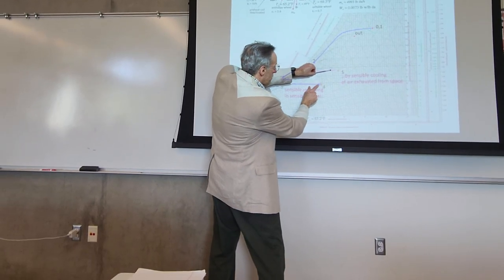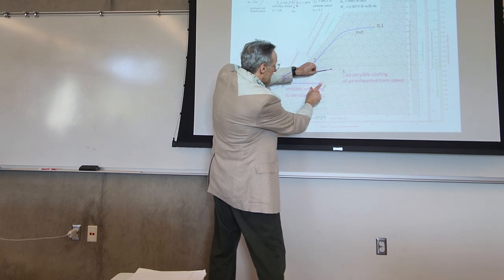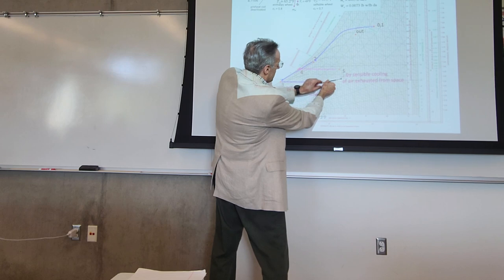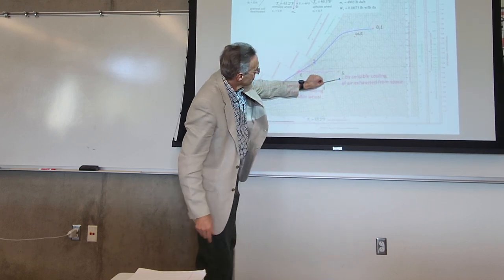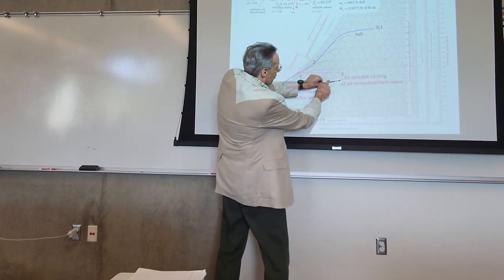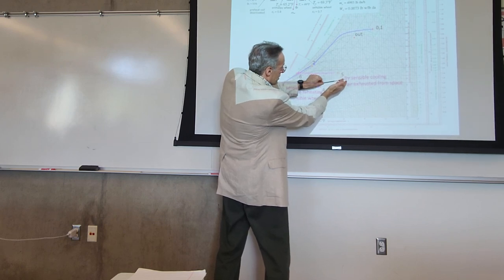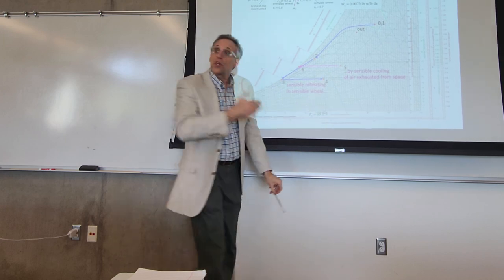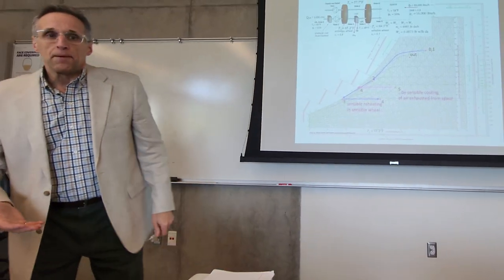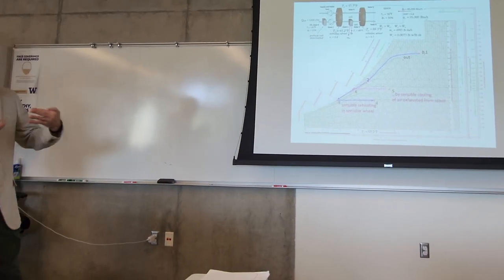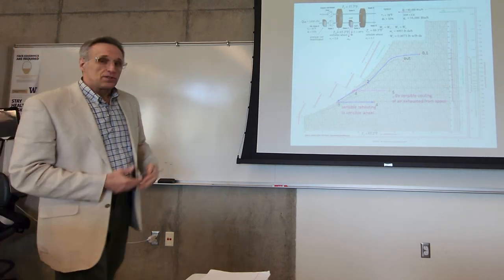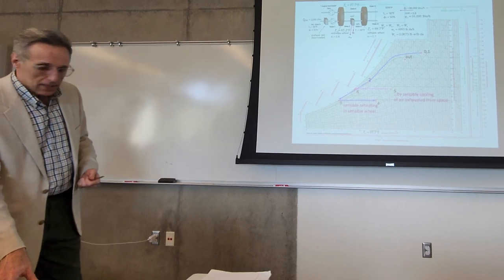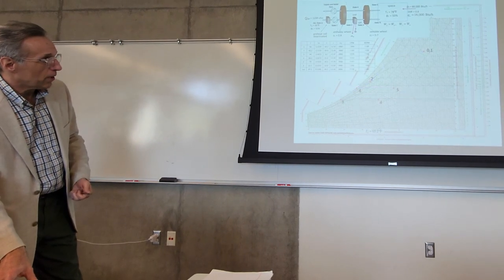So in this air, if you were to put this air into the room, it's going to warm up. It's going to follow a slope like this. It's going to follow that sensible heat ratio slope, and it's going to warm up, but it's going to be colder and drier than your set point. Okay, so thus the need for some other form of conditioning to bring the temperature and humidity to the desired set point.